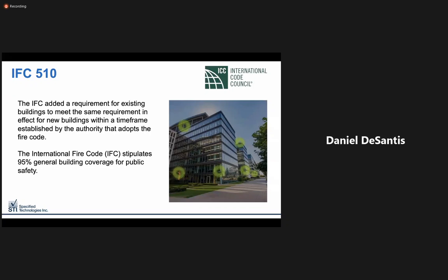Requirements for in-building emergency radio communication systems were first introduced into the International Fire Code in the 2009 edition of Section 510. Buildings that cannot support the required level of radio coverage shall be equipped with an indoor distributed antenna system, or DAS, with FCC certified signal boosters or a system that is otherwise approved. The IFC also added a requirement for existing buildings that did not already have an approved emergency radio communication system to meet the same requirements in effect for new buildings within a time frame established by the AHJ.